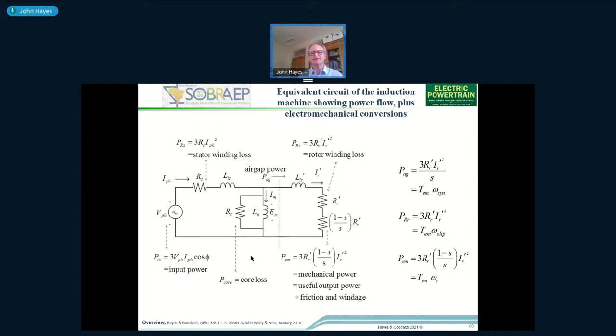And we can easily get into field weakening. That said, field weakening is a relatively simpler concept for an induction motor, in that there isn't much changing within the machine. We're just changing the slip and how we look at slip. By playing with the slip, we can introduce field weakening into the machine by default, by causing the magnetizing flux to reduce as the speed goes up.